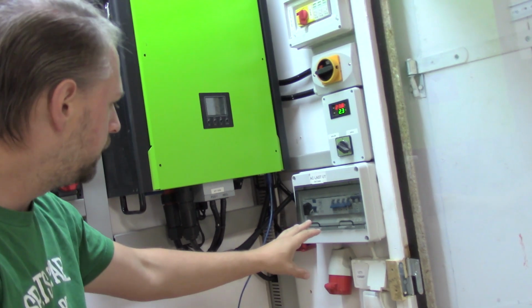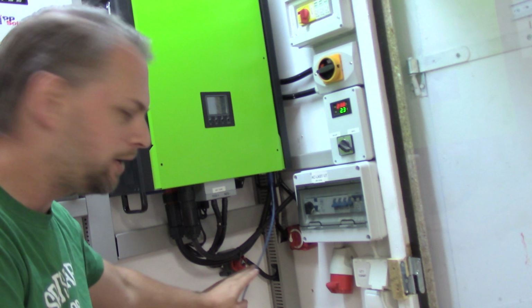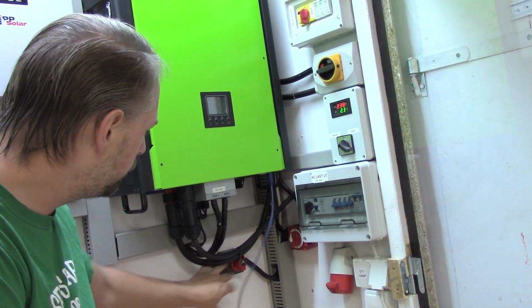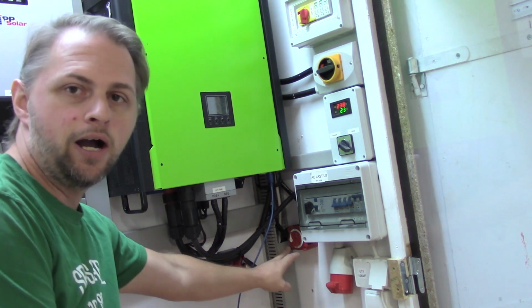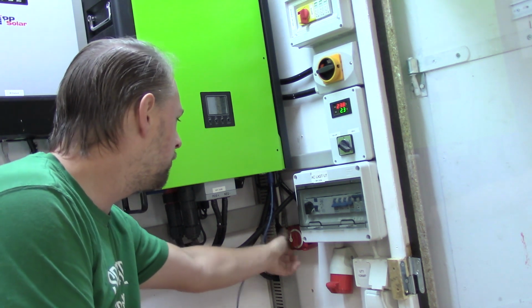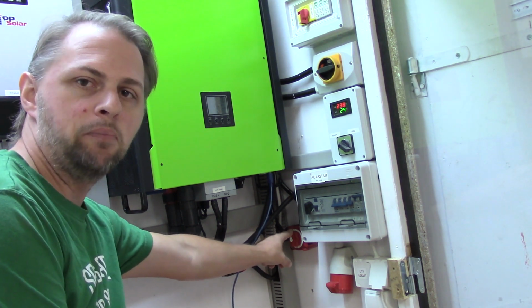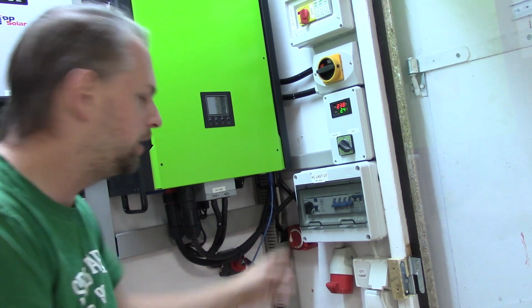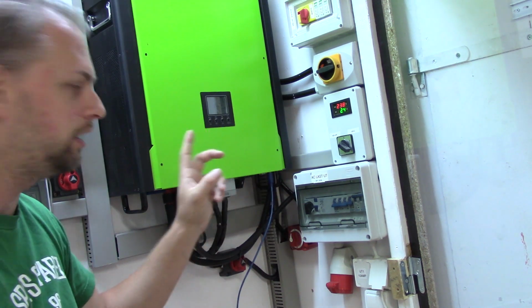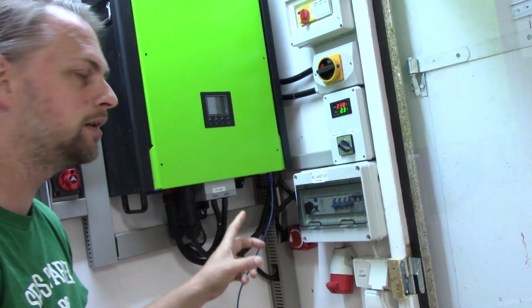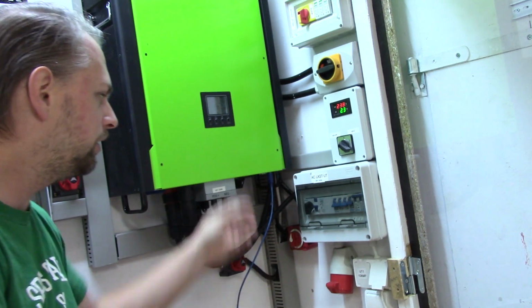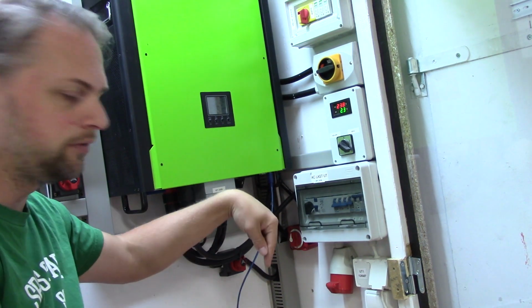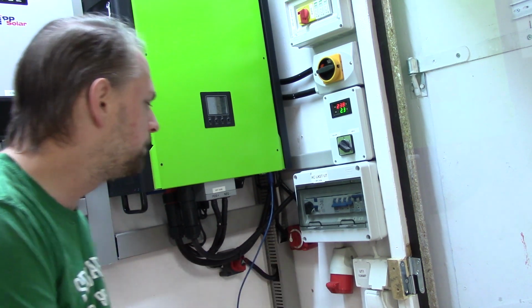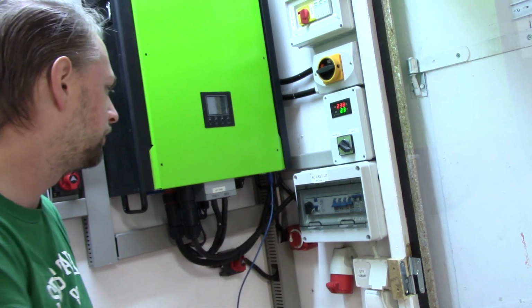If we take a look down here, we have even more stuff. We have the breaker here for the battery for this inverter. And then behind here, we have a switch pole that can switch between the battery banks. This one will be able to switch between the battery bank on top here, that is the lithium iron phosphate battery bank, roughly 80 kilowatt hours, and then we have another one below here that will be roughly 30 kilowatt hours.